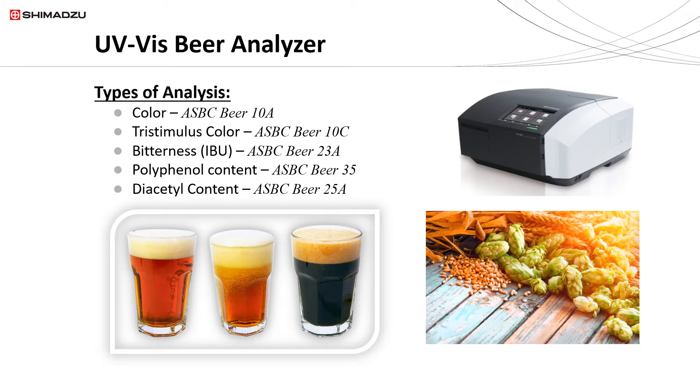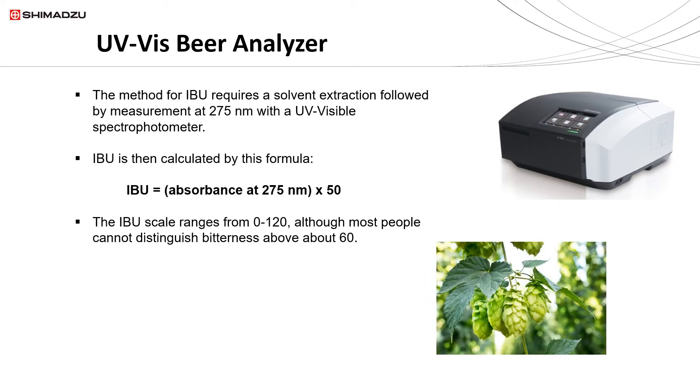The Shimadzu UV Beer Analyzer actually does five types of analyses according to various ASBC methods: you can measure the color, the tristimulus color, the bitterness, the polyphenol content, and the diacetyl content. The ASBC Beer 23A method for IBU requires a solvent extraction from the beer, followed by a measurement at 275 nanometers with a UV-visible spectrophotometer. It is calculated by a very simple formula: you take the absorbance at 275 nanometers and multiply it by 50.